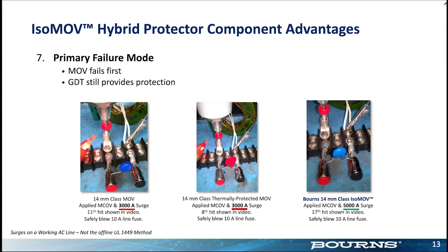If you're using these, you bought these to offer you protection, right? These are not inexpensive devices. These have a complicated structure to them, and that thermal fuse did not offer the protection you thought it would.